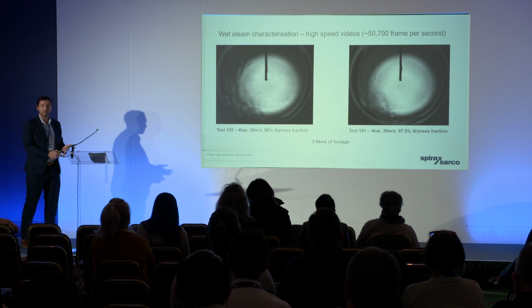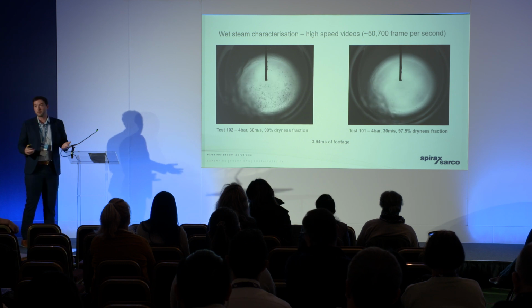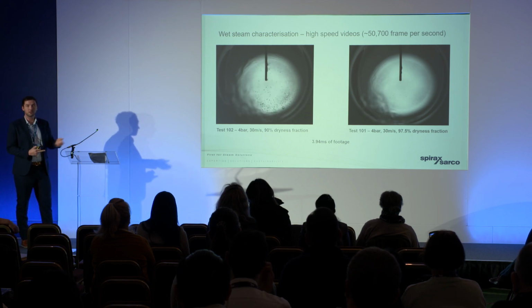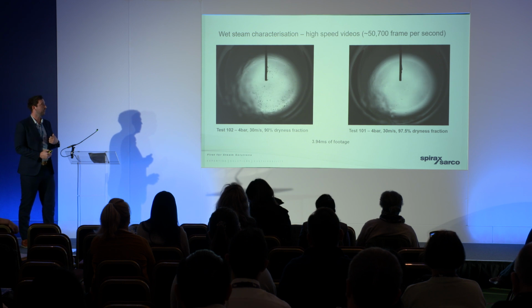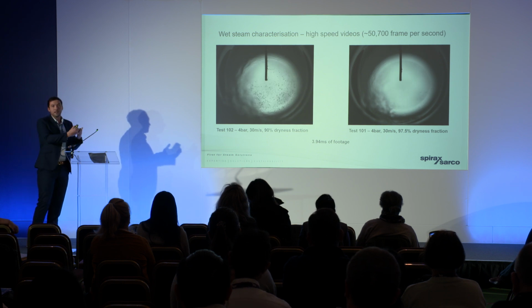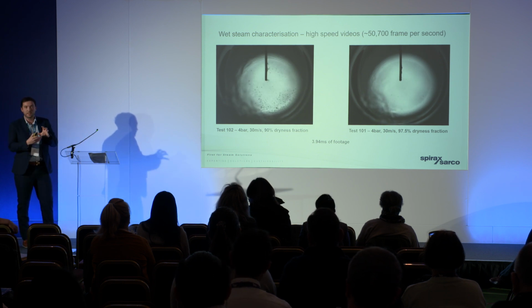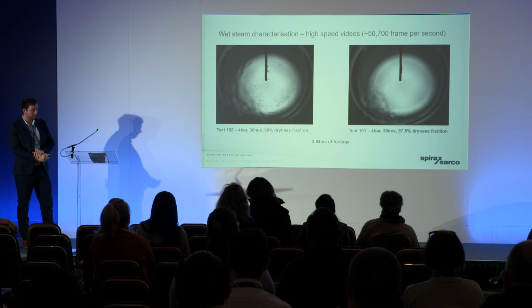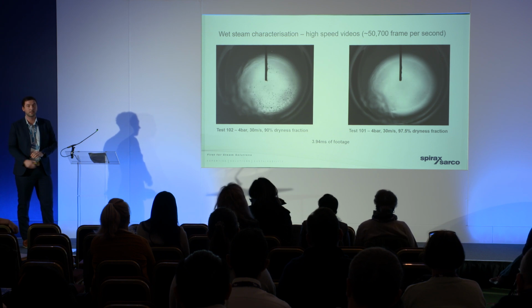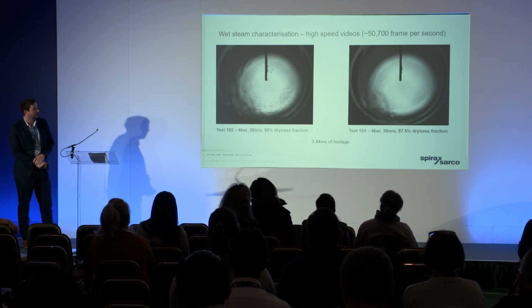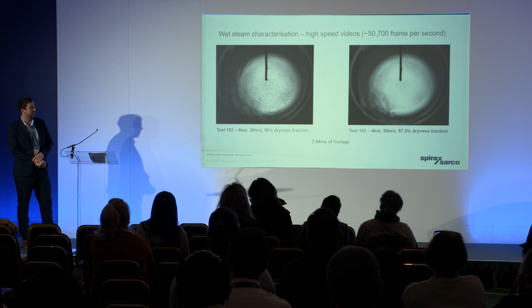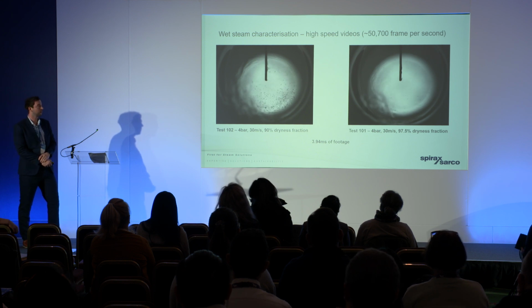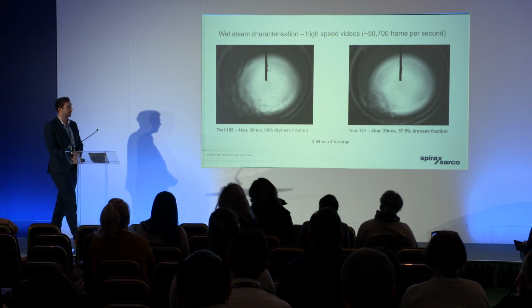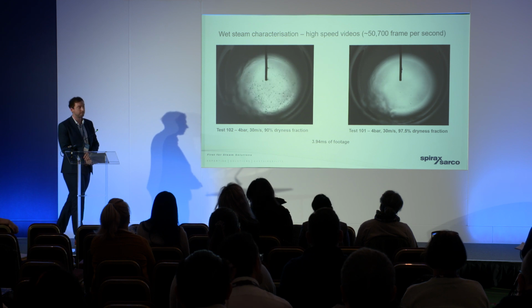They're causing corrosion because they could have chemicals in them. They're causing erosion because they're being dragged along at high velocity with the steam. They're colliding with equipment, with valves, with delicate instruments. So a lot of damage is caused by these water droplets, and also the heat transfer is massively reduced. You can see on the right-hand side, that's 97.5% dryness. So with EN285, this is the kind of quality steam that we're aiming for.